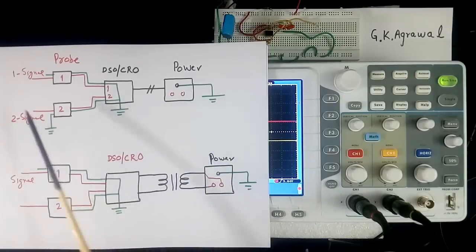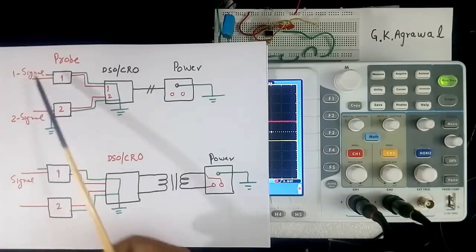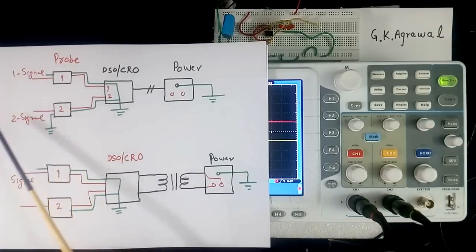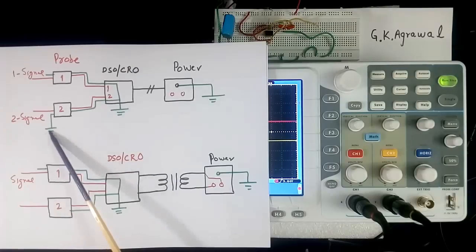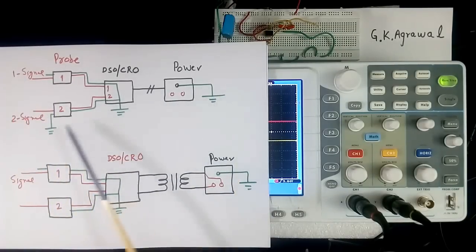Suppose here we are measuring 230 volt or 110 volt AC. Then common point, earth point of this incoming signal, and this power supply should be same. It should not be different.